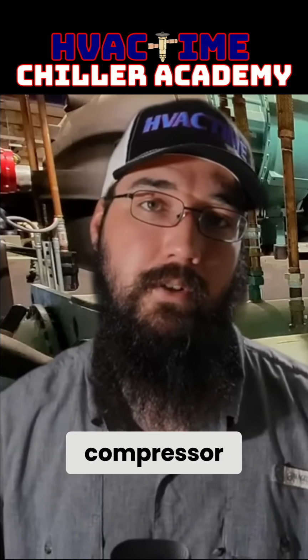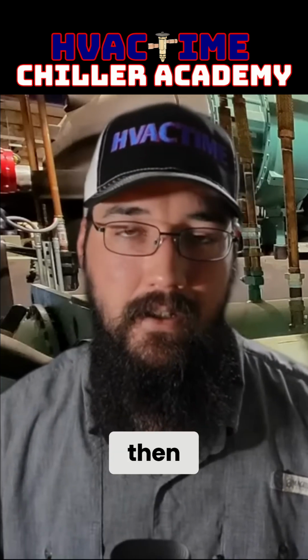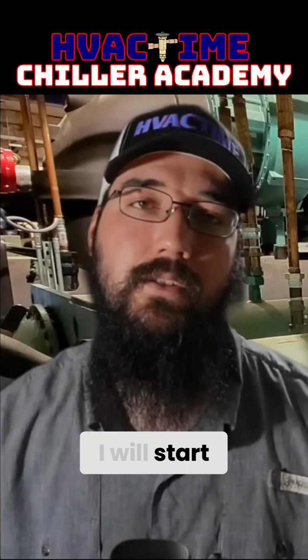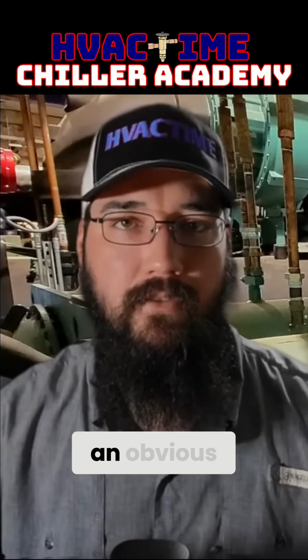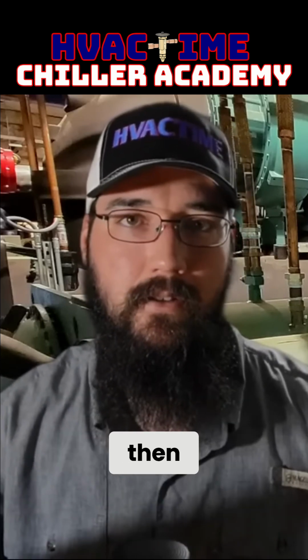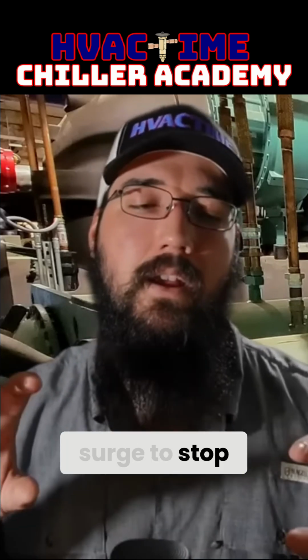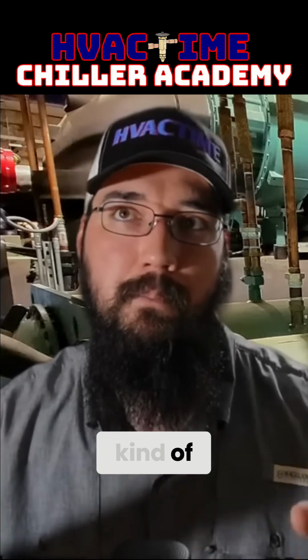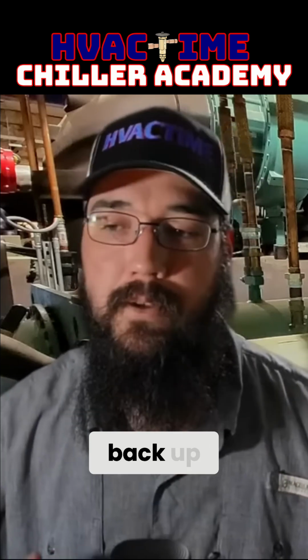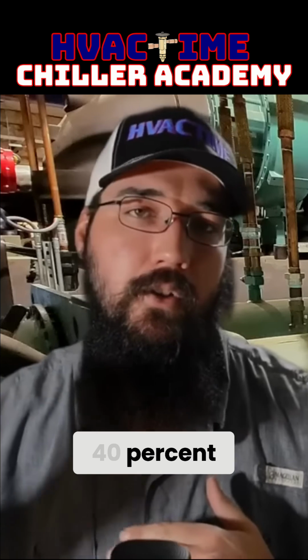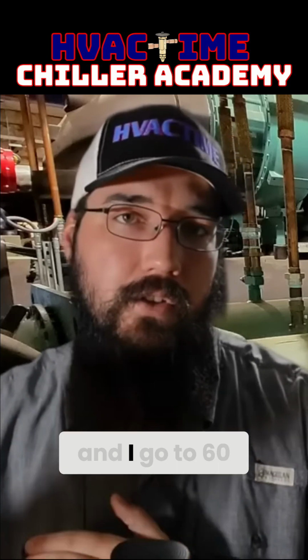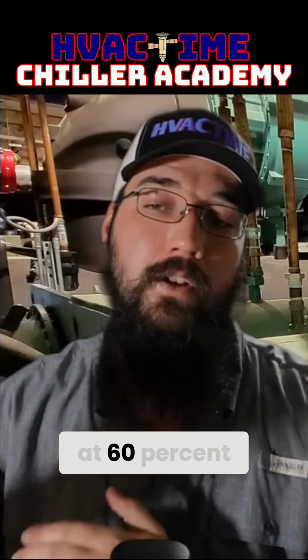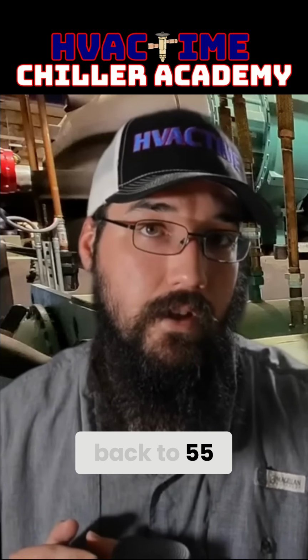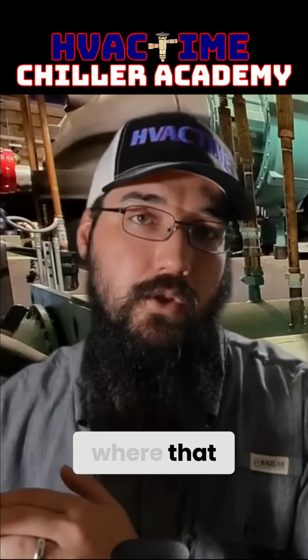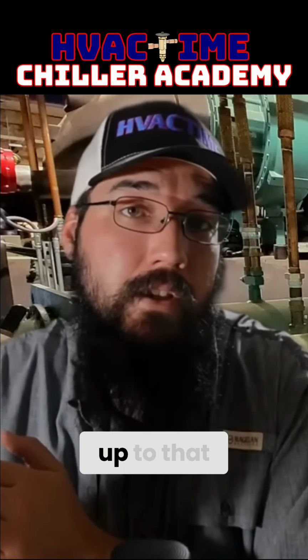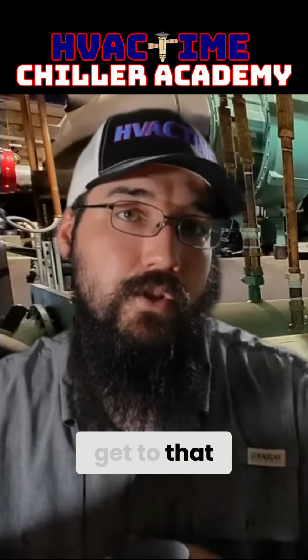Completely force that compressor to ramp down, then I will start slowly. If I don't have an obvious situation right then, once I've got the surge to stop, I will start bumping that current limit back up. Say I started at 40%, I go to 50, and I go to 60. Oh, I hit a surge at 60%. Okay, let's come back to 55, and then let's see where that surge line is. Let me push right up to that surge.